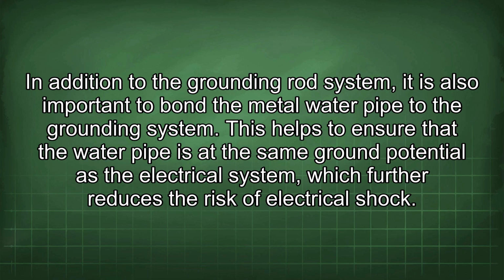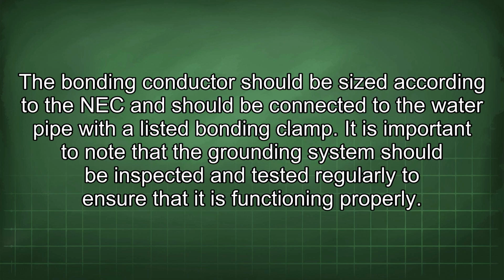This helps to ensure that the water pipe is at the same ground potential as the electrical system, which further reduces the risk of electrical shock. The bonding conductor should be sized according to the NEC and should be connected to the water pipe with a listed bonding clamp. It is important to note that the grounding system should be inspected and tested regularly to ensure that it is functioning properly.